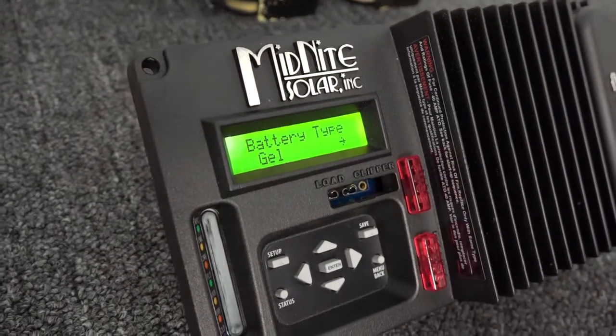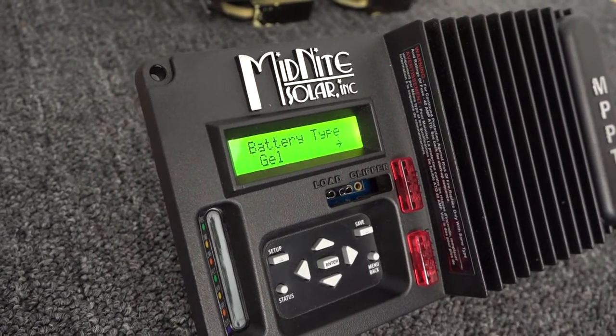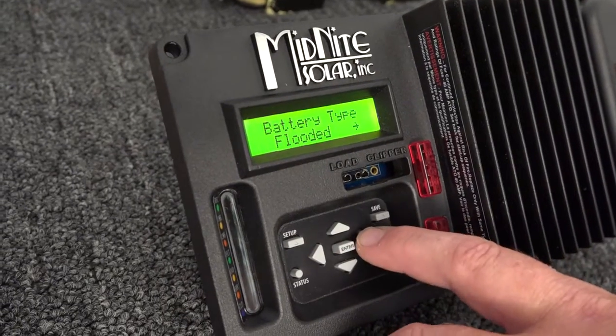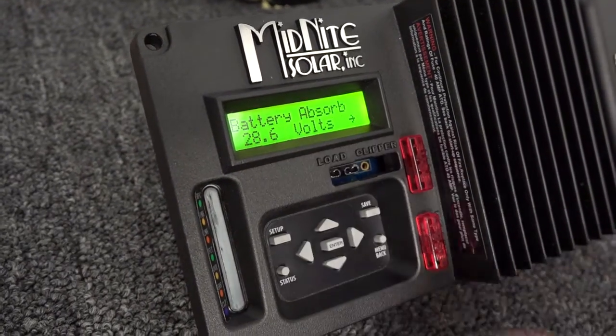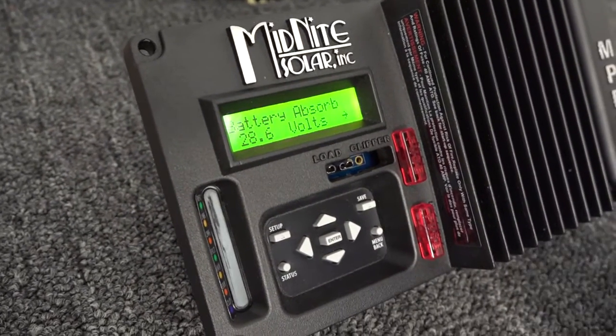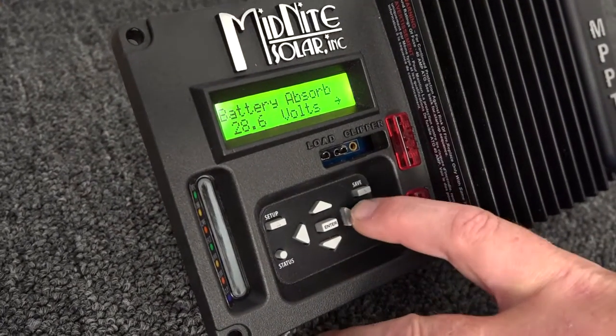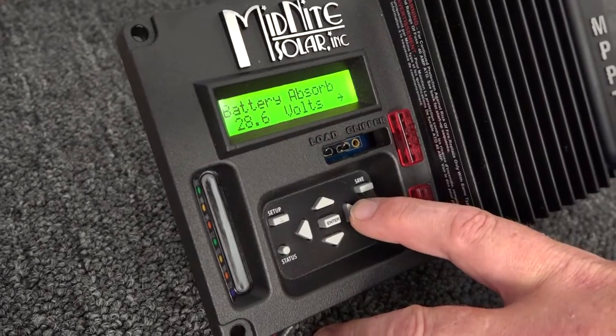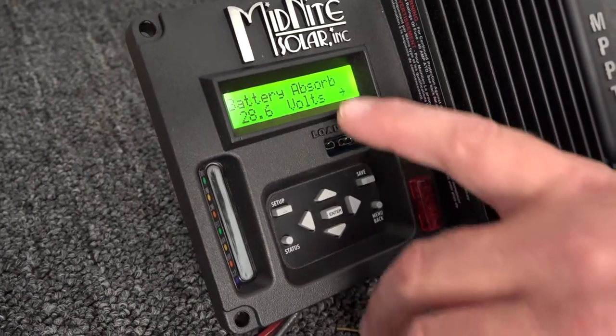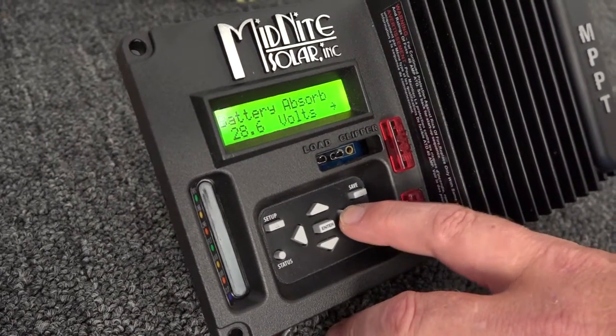All this is doing for us is giving us things like default charging parameters. We still highly recommend that you get the actual charging parameters from your battery manufacturer and enter them here. The absorb volts is shown as 28.6 — this is a value your battery manufacturer will give you, not a value that we provide. It's very crucial these are correct according to your battery manufacturer, because you will destroy your battery by undercharging or overcharging. Absorb is sometimes called bulk — you'll hear it referred to by both terms.